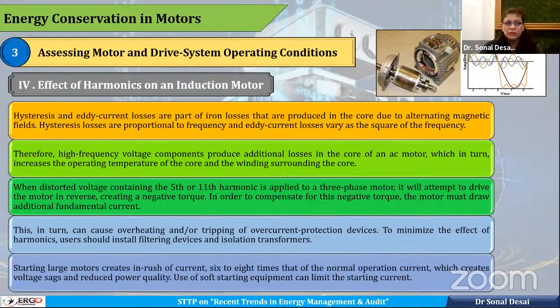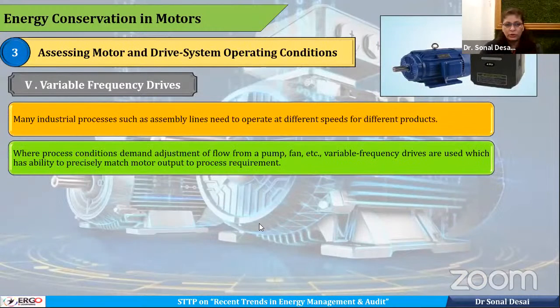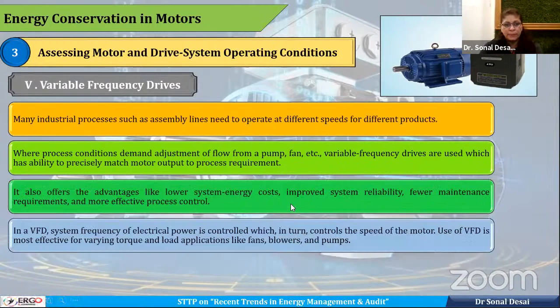Use of a VFD with the motor is advisable in particular industries. So that list is shown over here. Wherever different speed applications are there, in an assembly line or a pneumatics line, the use of a VFD is advisable. Wherever a process continuously demands adjustment of flow from a pump, fan, etc., where the flow rate keeps on varying, there the use of a variable frequency drive is advisable. They have the advantages of lower energy cost, improved reliability, fewer maintenance needs, and more effective process control.